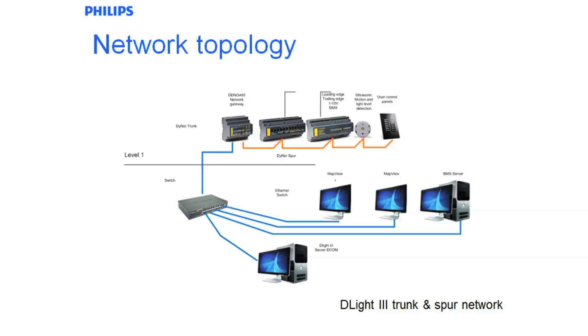However this time we are using an Ethernet layer. When we go to this level of integration, we effectively have a DLight III server and Map View layer talking in Ethernet up a trunk. In a modern day building you would normally see a fibre trunk running up the building with a services switch on each floor to carry data for security and also BMS systems, typically running BACnet over IP.